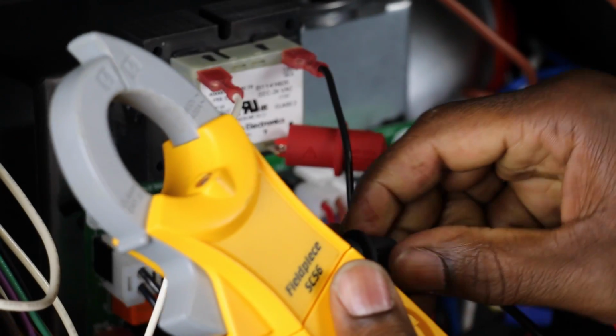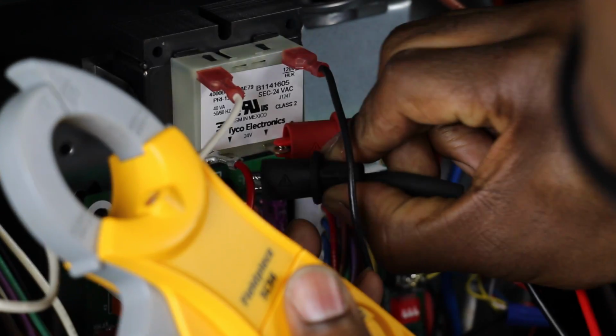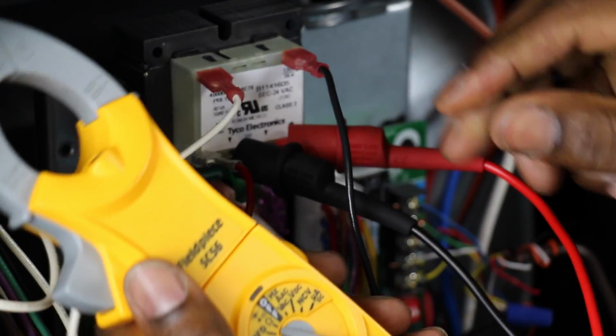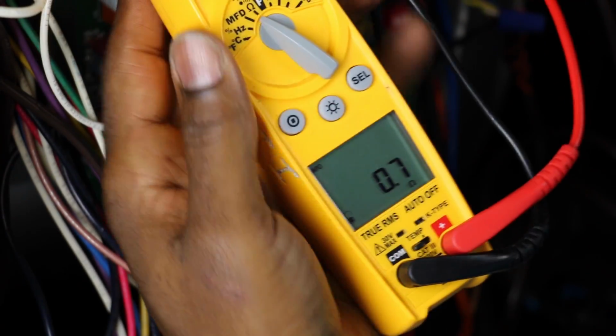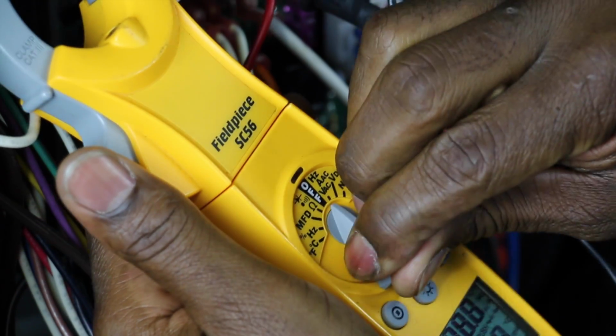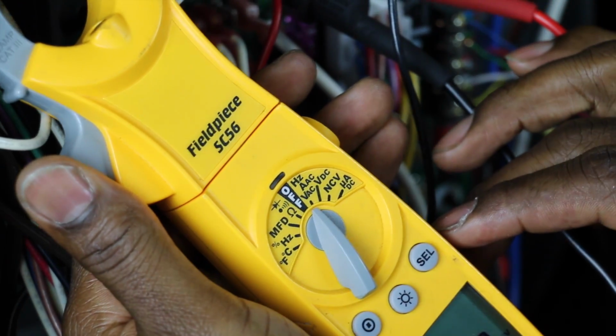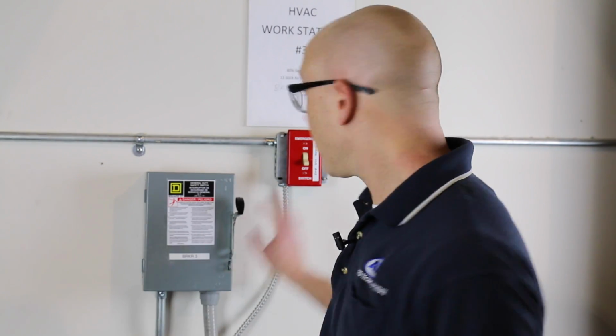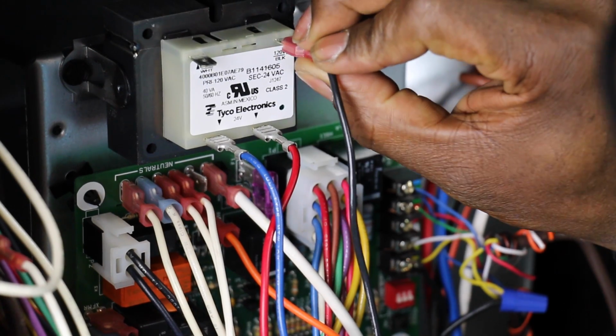Applying the alligator clips to the secondary side of the transformer, we can see that the resistance here is less than 1 ohm. The next step will be to check the voltage of the transformer. The gas furnace has a door switch on it, which means that we can energize our switch here and then use our door switch as the disconnect for power whenever we're troubleshooting it.